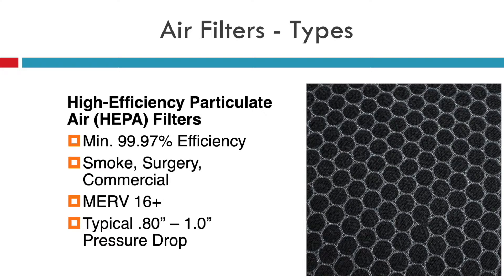The highest efficiency filter would be the high efficiency particulate air filters, or HEPA filters. These have a minimum of 99.97% efficiency in order to meet the UL listing and are also used to remove smoke in hospitals and commercial applications. They have a MERV rating of 16 and above. With HEPA filters, the typical pressure drop can be 0.8 all the way up to 1 inch, and they're not usually used in residential HVAC applications because of this unless they're standalone units.